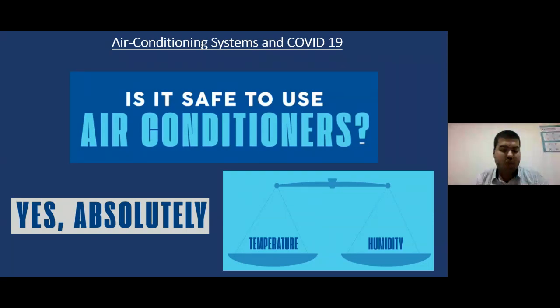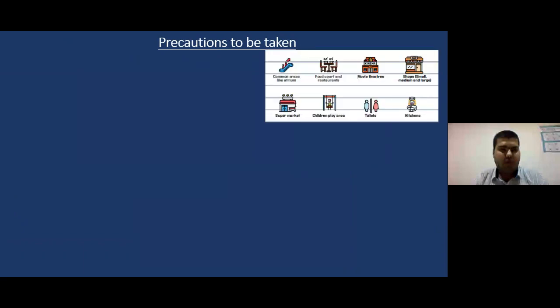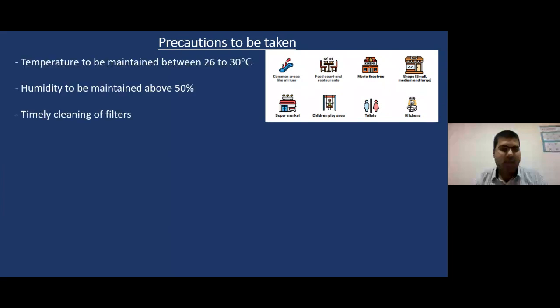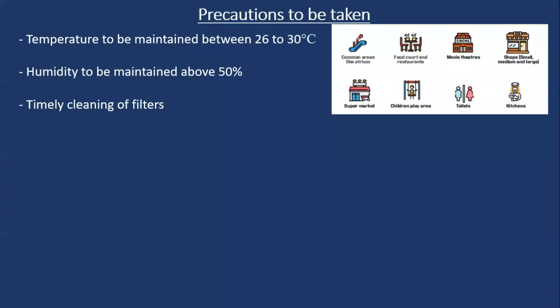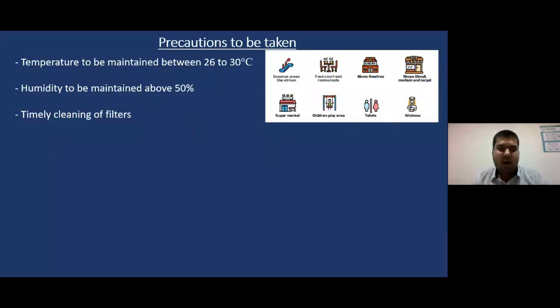So what are the basic precautions we need to take? The basic precautions to be taken by the customer in areas like a movie theater, a shopping mall, a food court or restaurants are that the temperature should be maintained between 26 to 30 degrees Celsius. The humidity should be maintained above 50 percent. In some cases, you might have observed that some people say you should keep a bowl of water in the room so that it maintains the humidity in dry conditions. Also, timely cleaning of filters is very important, which is the most neglected concept in the air conditioning field. So that is very important in this scenario.